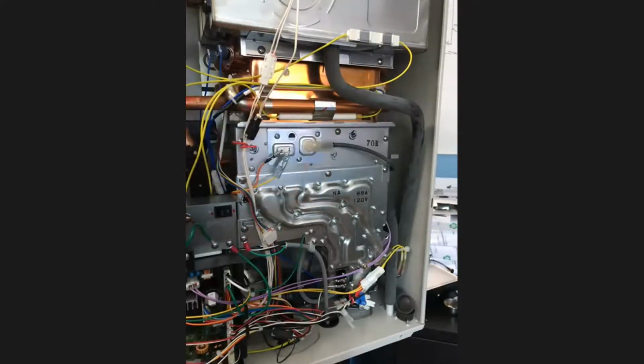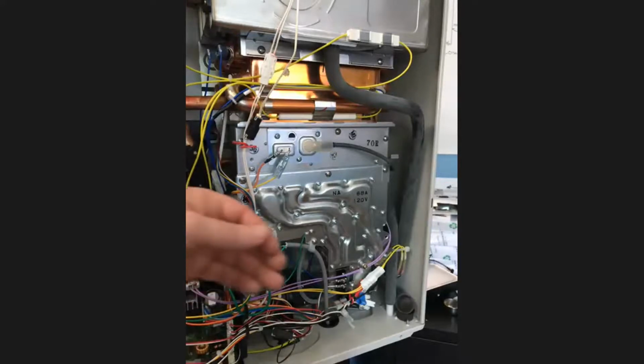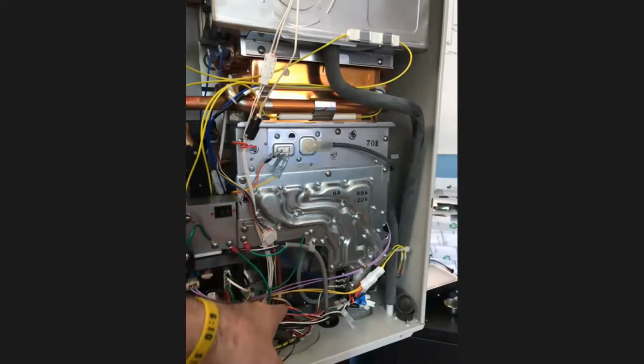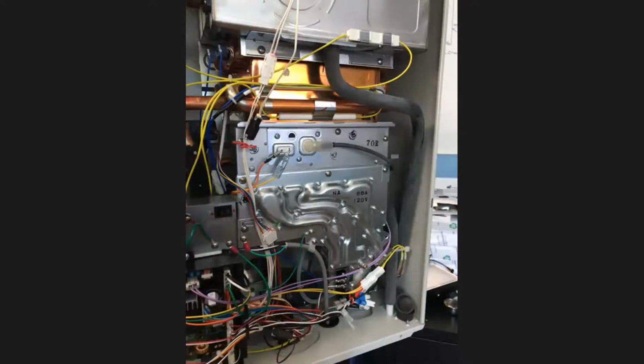So the sequence of operation: I get that half a gallon of water flow coming through, which turns everything on. My fan turns on, then I spark, and I open my gas valves - whichever one I'm looking at at that point in time. Then I can modulate those valves up and down to match my load, whether it's a small load or large load.